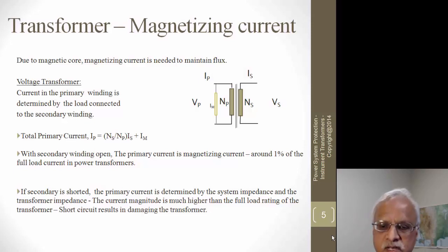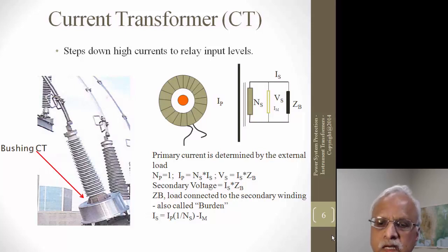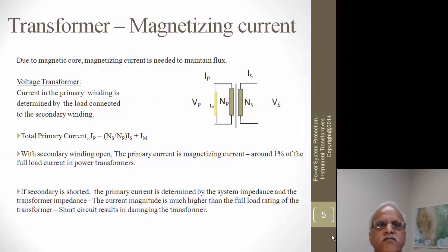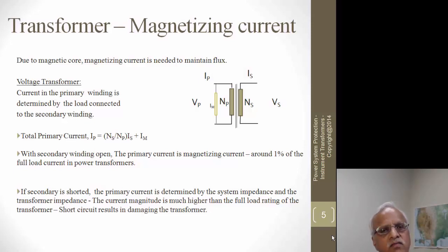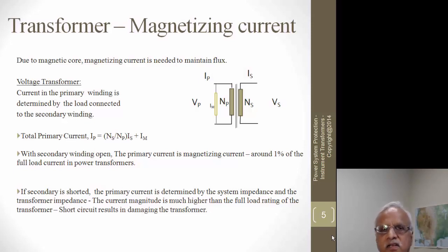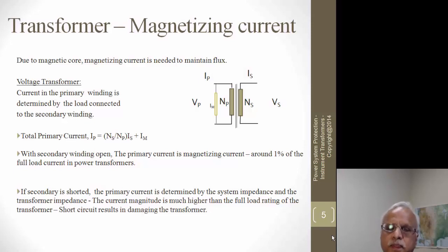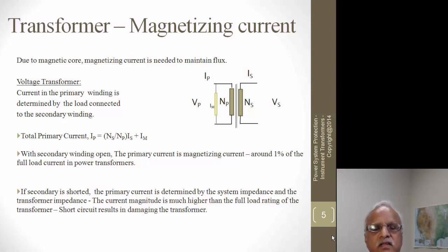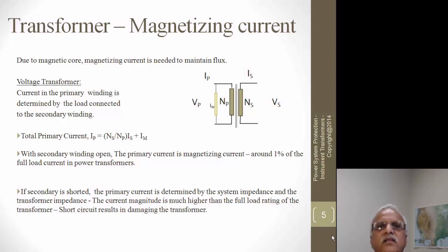If we keep the secondary side open on a voltage transformer, you will just see the magnetizing current flowing on the primary side, which is only about one percent. But if you short it, the short-circuit current could be 10 to 20 times the normal rating of the transformer, and you might damage it. The current is only limited by the impedance of the transformer and the source.